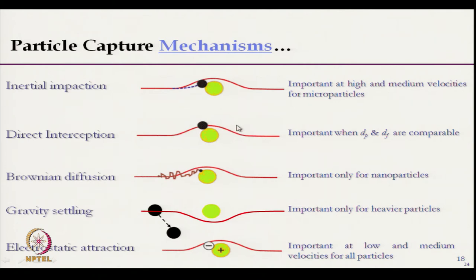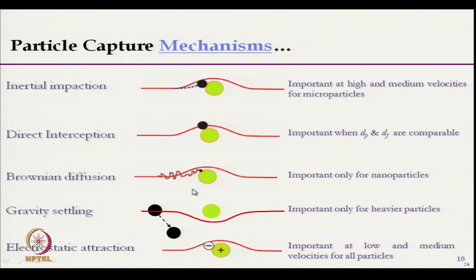In direct interception, particles with lower size and lower inertia can follow the air path and get trapped inside the structure where the particle diameter is higher than the diameter of the pores. In Brownian diffusion, due to Brownian motion, particles strike the fiber surface and settle. In gravity settling, the mass of the particle causes it to separate from the air stream. Electrostatic attraction occurs due to different charges.